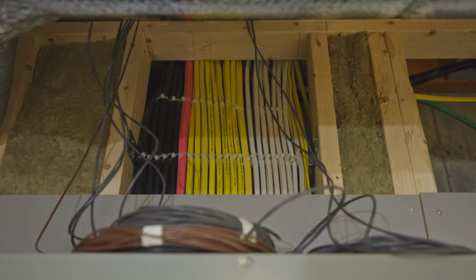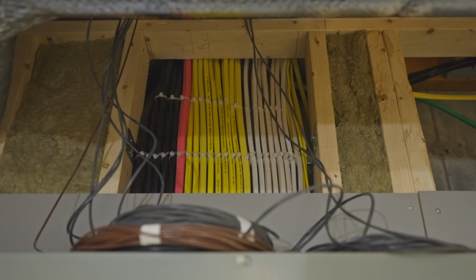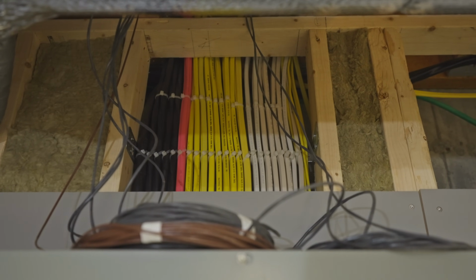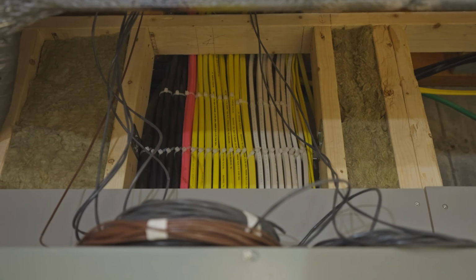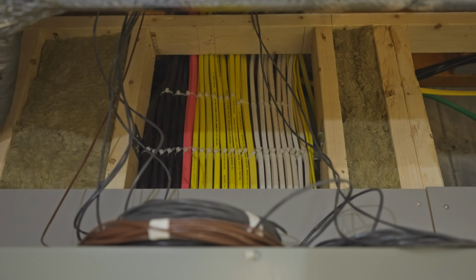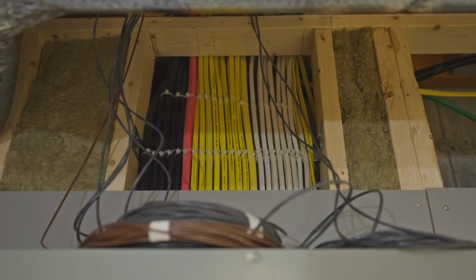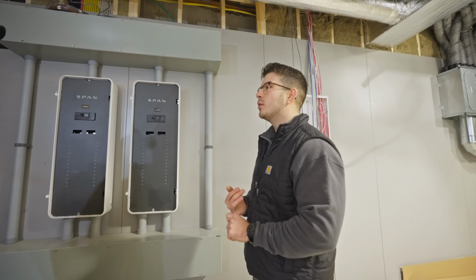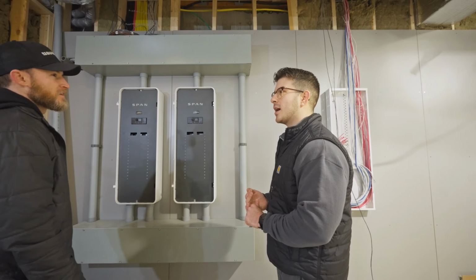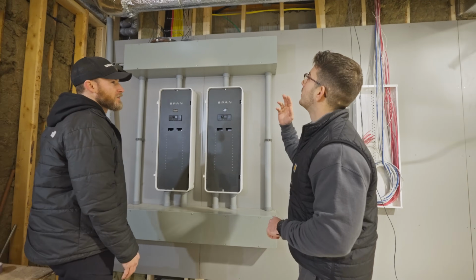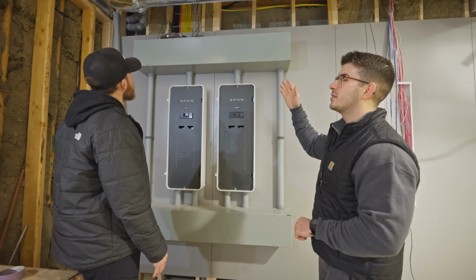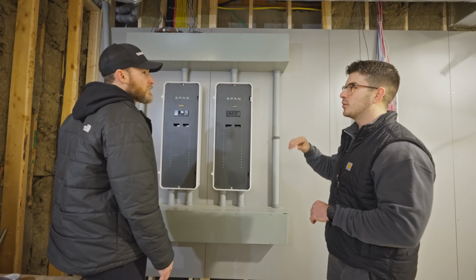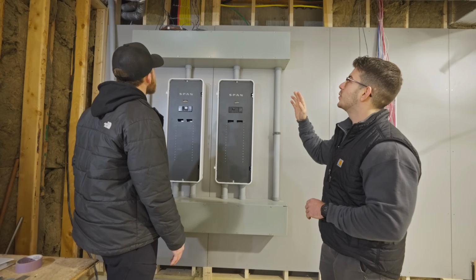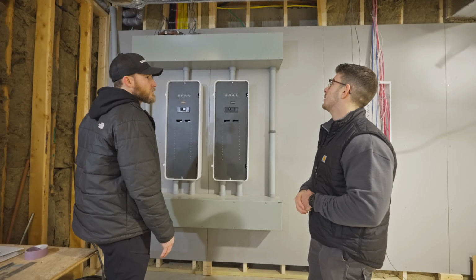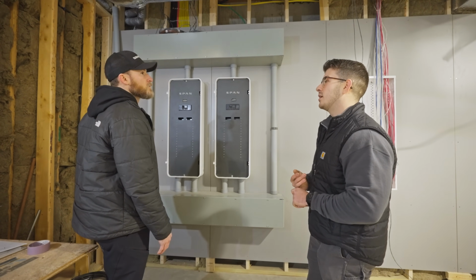Pretty basic question, but you have white, yellow, red, black wires. It's color coding for the gauge of the cable. Our whites are 14 gauge, yellow is 12 gauge. The code's changing again, so 14/3 is now going to be blue, and 12/3 I believe is now red. We have our 10 gauge, which is pink, and 10/3 is pink now. Those go out to our wall ovens. Then those black cables are all 6 gauge for the condensers and the cooktop.